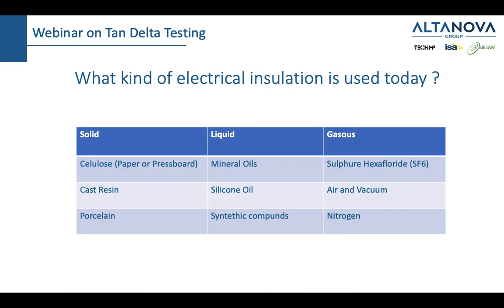Today, when we talk about insulation, we have a few types: solid insulation, liquid insulation, and gaseous insulation. Solid would be cellulose, which is paper and pressboard, which you will often find in a power transformer, for example while wrapping the primary or the secondary winding. We can also use cast resin as a type of solid insulation, and porcelain, which is very often used, for example, for bushings and similar current and voltage transformers.